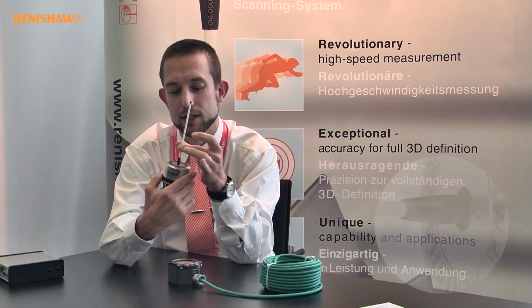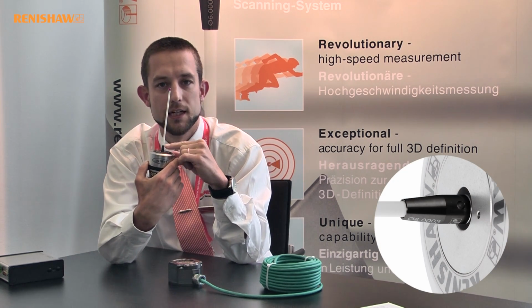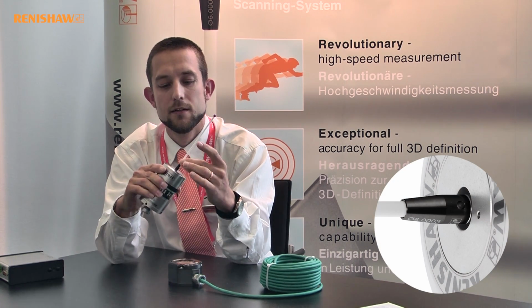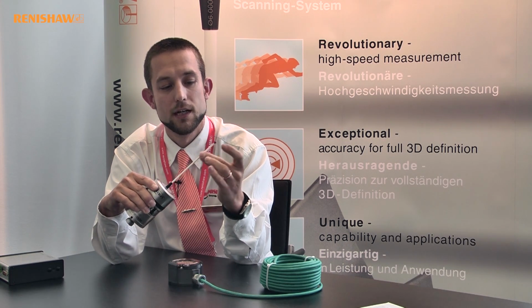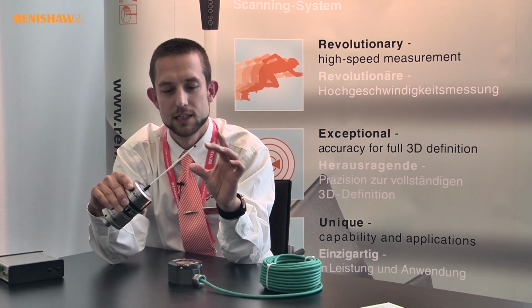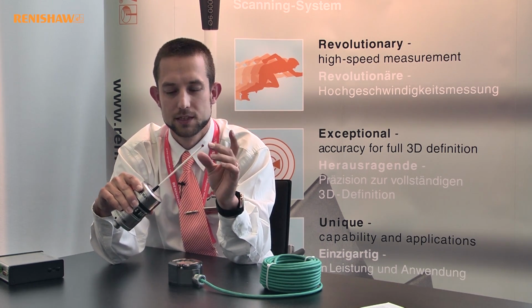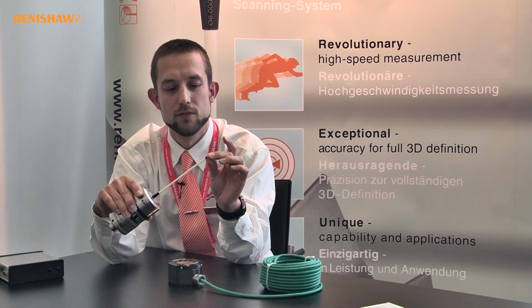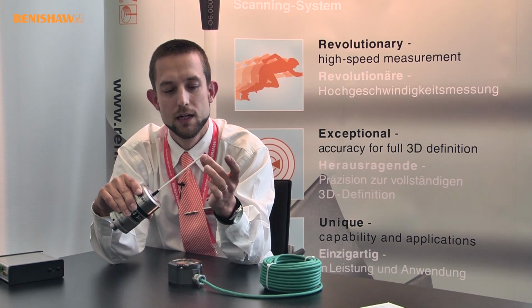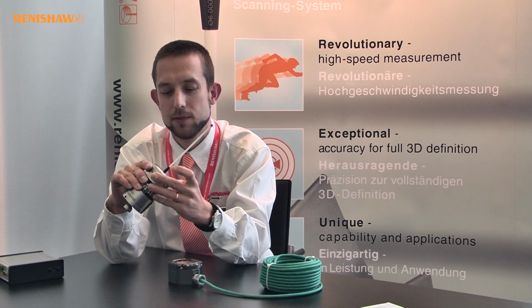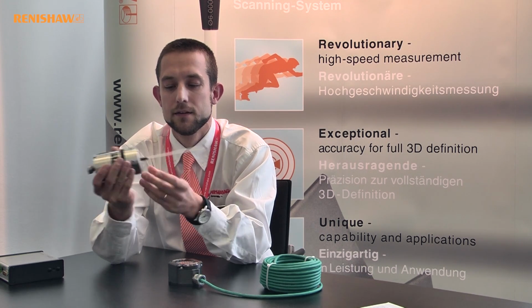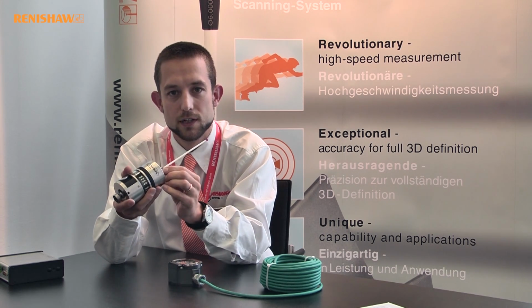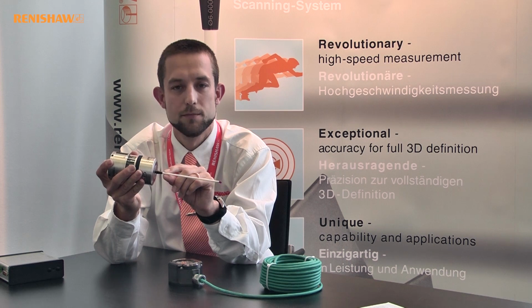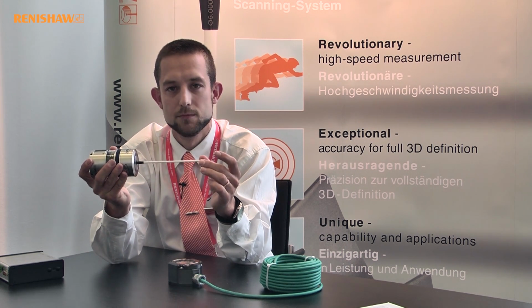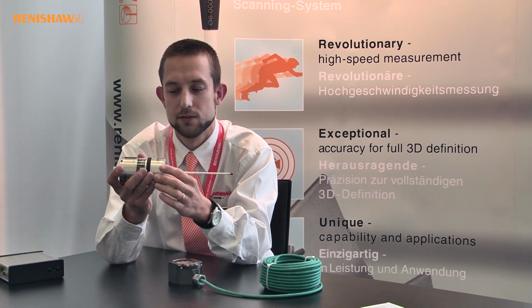You'll also notice on here that the stylus has got a number engraved on it. That's one of the differences. There's also a much thinner stem on the stylus, and that's because when you're scanning, the probe is constantly deflected, and therefore you need more clearance between the ruby ball and the stem to allow you to make a bigger scanning measurement range. The number is engraved on here for increased accuracy, so you can use this number when you set up the Sprint system to really give yourself the best accuracy during scanning.